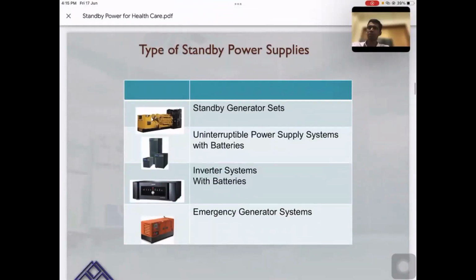Okay, I just explained the power supply requirements and the type of loads and the equipment that is coming in for the electrical distribution for the hospital. Now, we will look at the standby power supply systems that are actually available and what is practically employed in our modern projects. We have the first item as the standby generator sets. We also have UPS systems, which is actually for the critical digital equipment. Then we have the inverter systems. Basically, it's a lower cost equipment compared to UPS systems. It feeds the lighting and non-critical emergency systems.